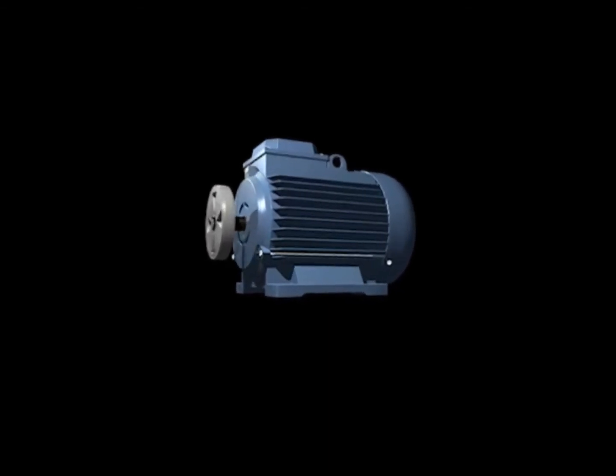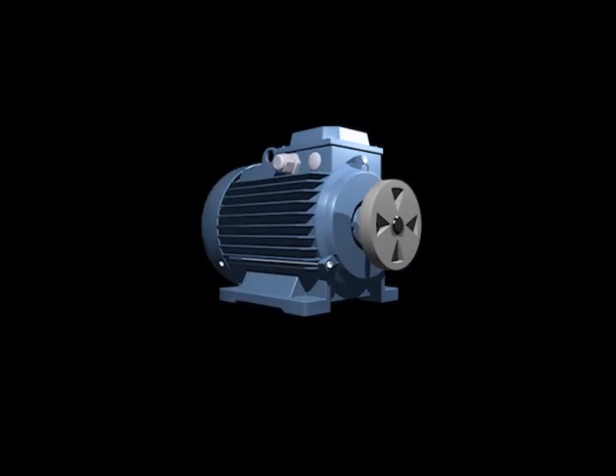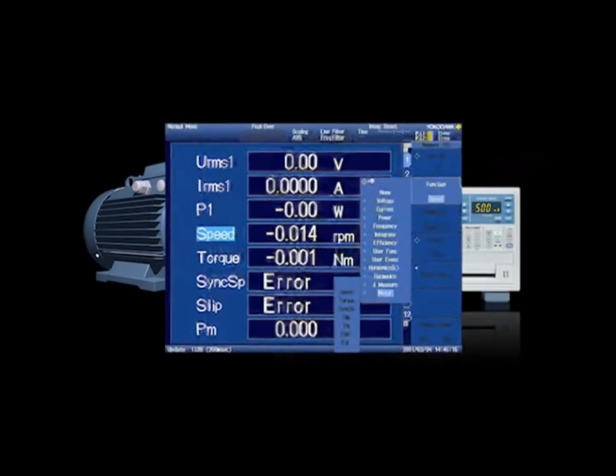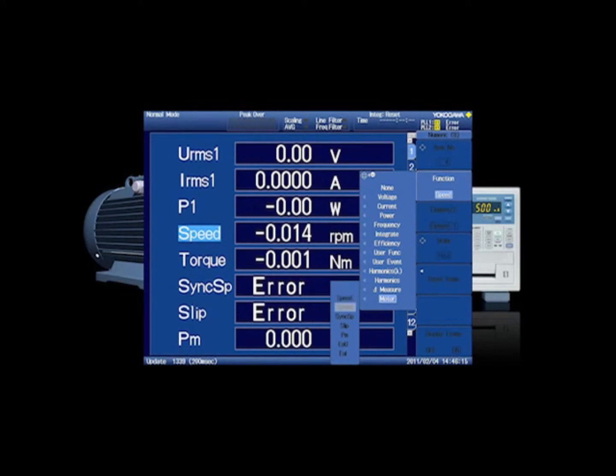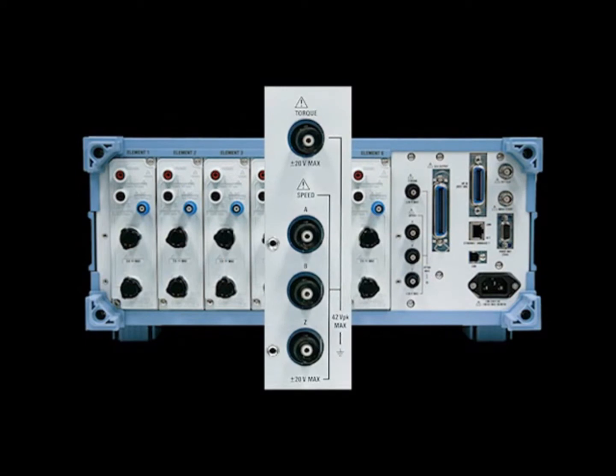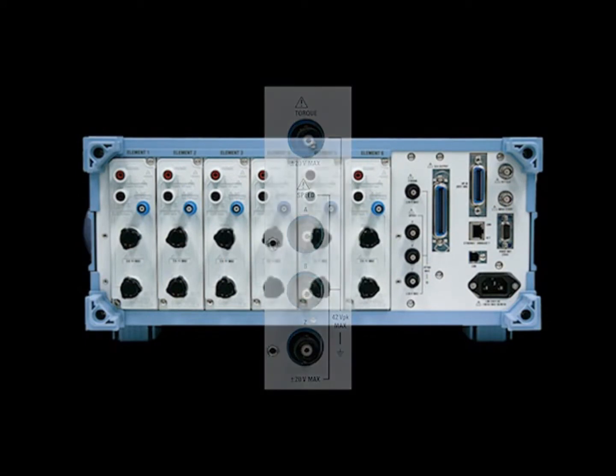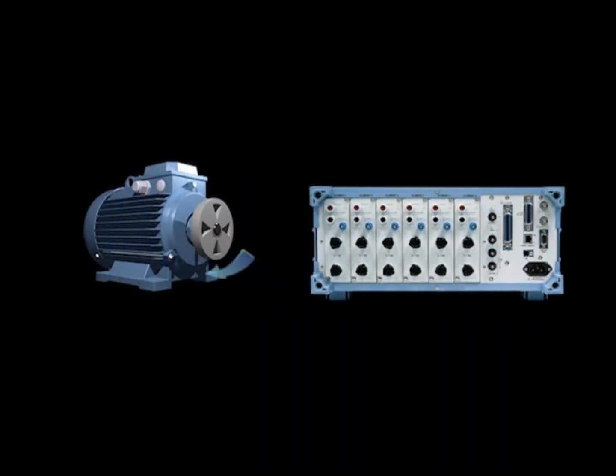For electric motor testing applications, the WT1800 offers a unique and powerful motor evaluation function. In one unit, you can measure all the electrical power parameters along with rotation speed, torque, mechanical power, synchronous speed, slip, motor efficiency, and total system efficiency. In addition, A-phase, B-phase, and Z-phase input terminals have been added for advanced motor analysis. These signals make it possible to detect the rotation direction of the motor. The electrical angle can be measured using the Z-phase signal.